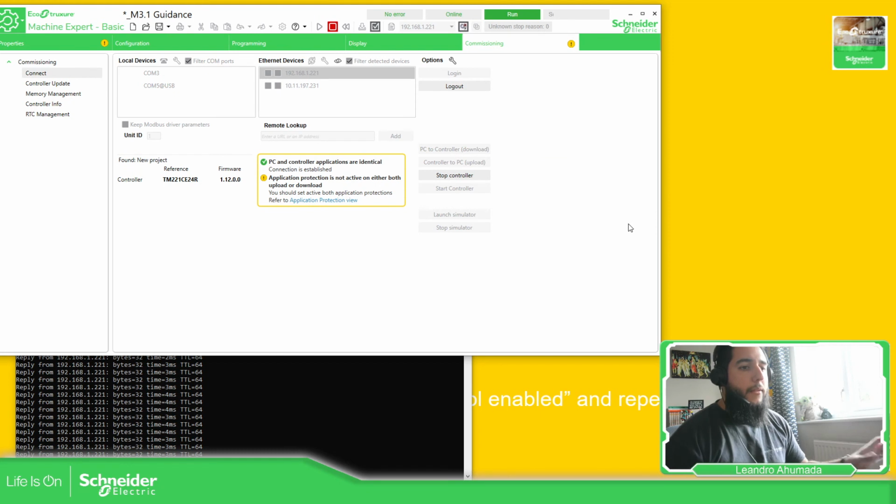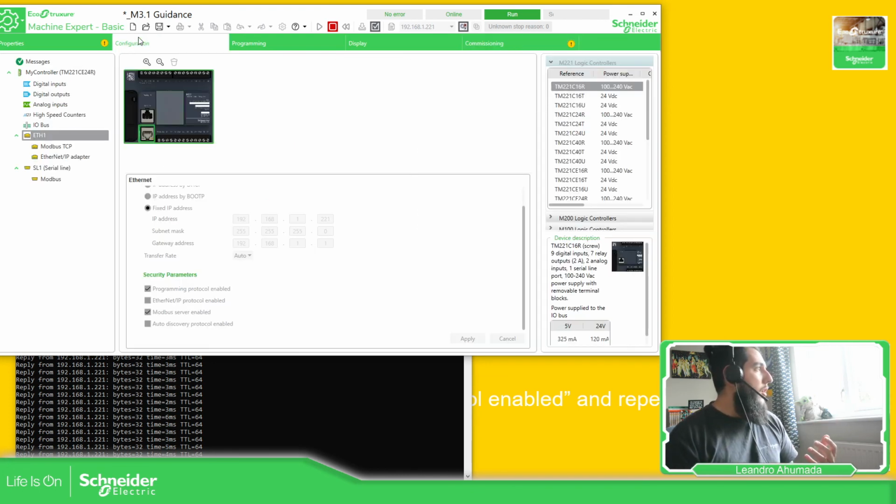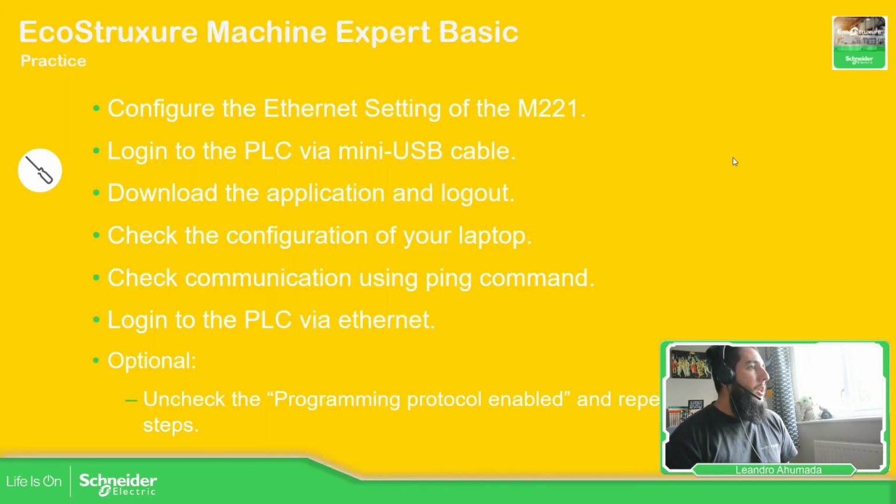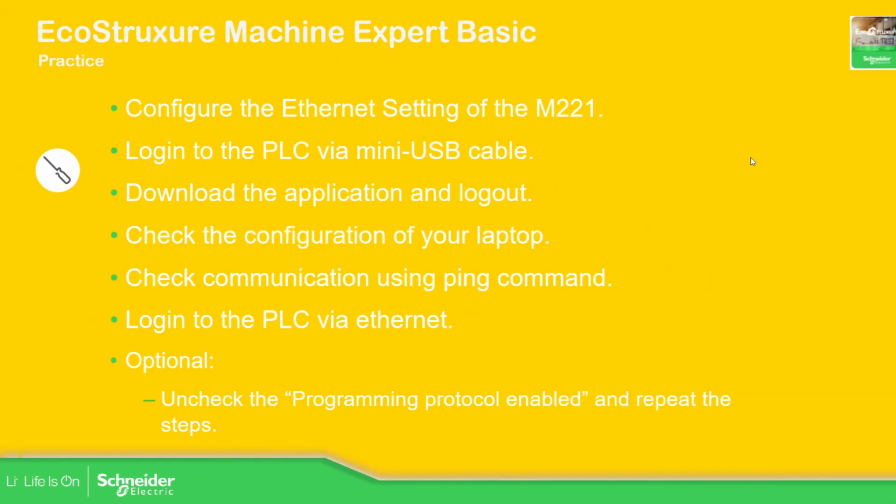So it's important that you define how you want the IP address of the PLC to be made. You can select DHCP, so the server assigns the IP address, or you can use a fixed IP address. And it's important that you select this programming protocol enable, so you can see the behavior that you have if you haven't selected that.